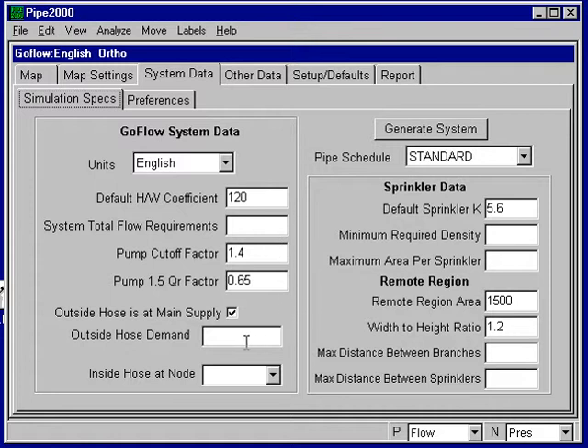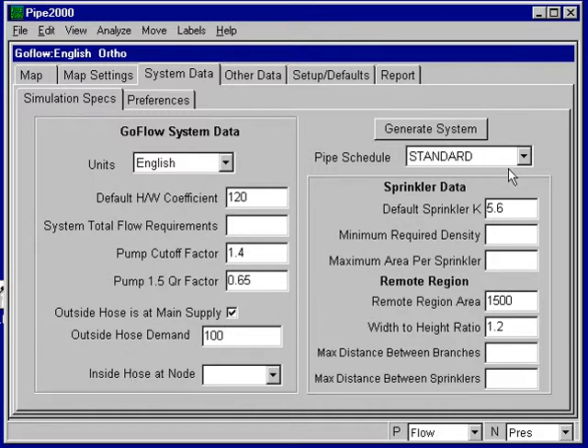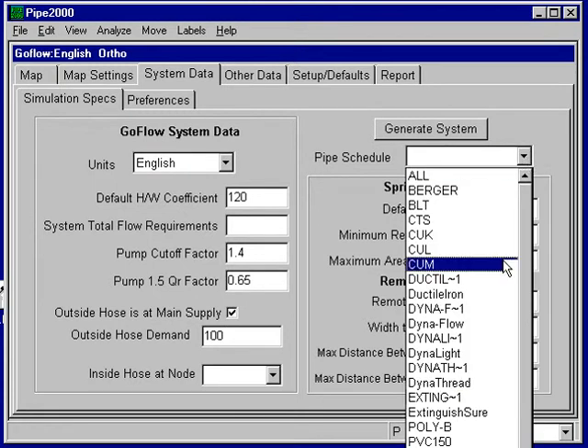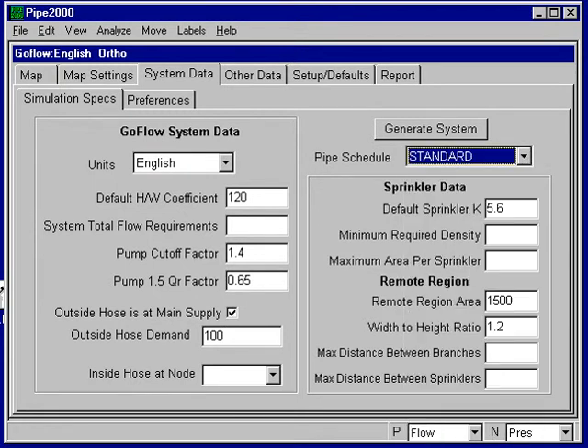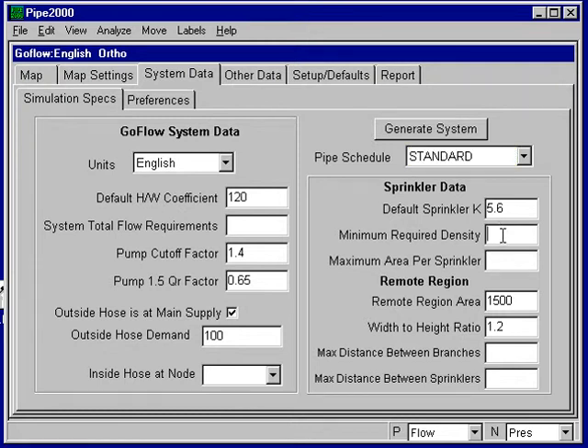I have an outside hose of 100 gallons per minute, which I'll enter there. The pipe schedule is standard. That's what I want. To get that, you just select it from the list that pops down. The density is 0.1 gallons per square foot, and the maximum area per sprinkler is a 20 by 20 spacing, so it's 400 square feet.